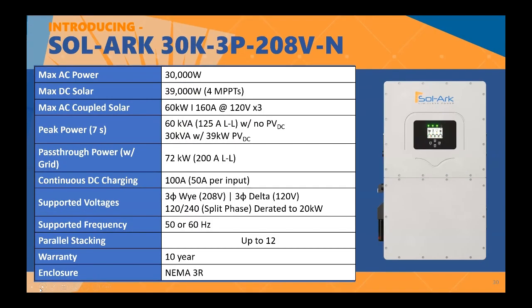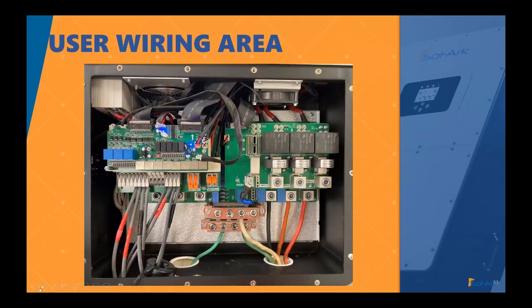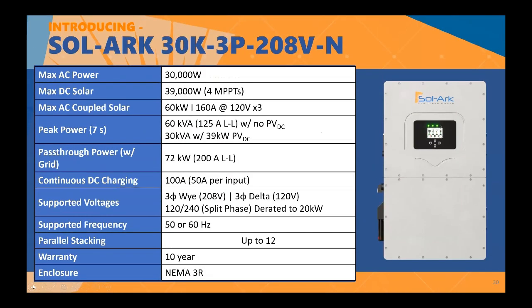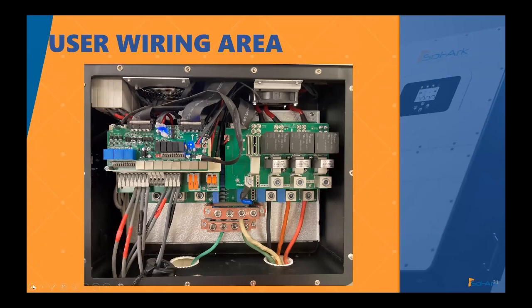All right, so just as we mentioned before, here are some of the specs for the 30K. The max AC power that you can input into this unit is 30 kilowatts, and the maximum DC solar is 39 kilowatts. You can distribute this into the 4 MPPTs by inputting 9.75 kilowatts in each MPPT. As I already mentioned, you can AC couple into this inverter. You can AC couple 60 kilovolt amps with no PV, and the preferable combination of AC and DC would be 39 kilowatts coming from PV and 30 kilovolt amps from the AC coupling solution that you choose.